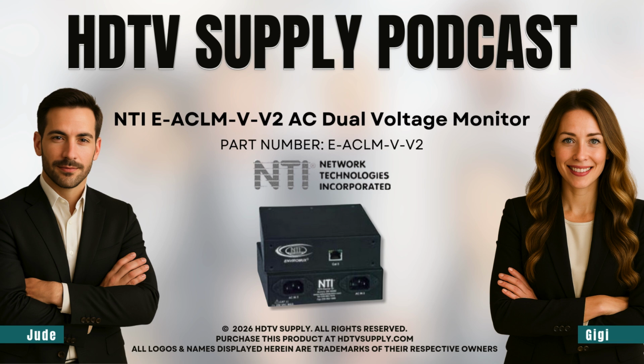And it all runs over standard CAT5 cable. For up to 1,000 feet, I see. But what if that's not enough? Well, that's where the flexibility comes in. Right, it's compatible with a fiber extender. So you could put this sensor up to 1.2 miles away from the main unit. That's incredible. It is. And that, plus the fact that it auto-configures as soon as you plug it in, makes deployment surprisingly easy. And it's powered by the main system, too. Yep, it sips power, just 70 milliamps. It's really designed as a low-draw monitoring satellite. And with CE and RoHS approvals, it's ready for pretty much any market.